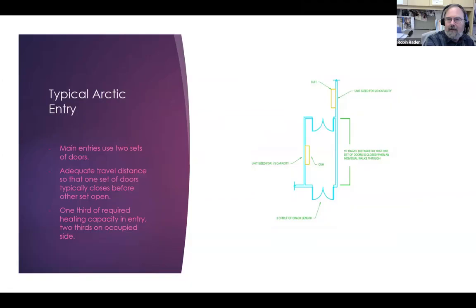design delta T. So when you get that number, you should put 1/3 of that heating requirement in the vestibule itself, and you should put 2/3 of that heating requirement just outside the vestibule. So the 1/3 will keep the sprinkler head from freezing. It'll keep the floor reasonably warm. And so this will be a tenable environment within the entryway itself. The cabinet unit heater outside the vestibule picks up the cold air that gets through as people pass through this entry.